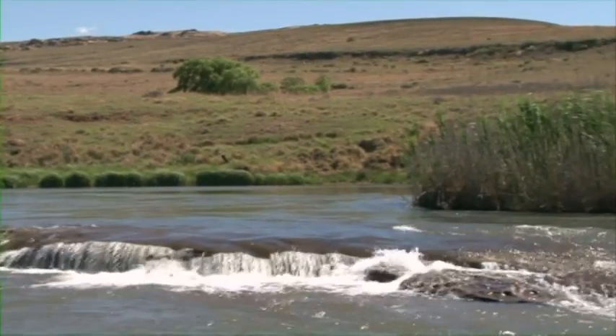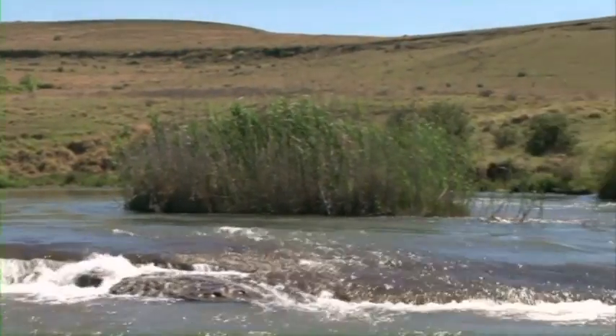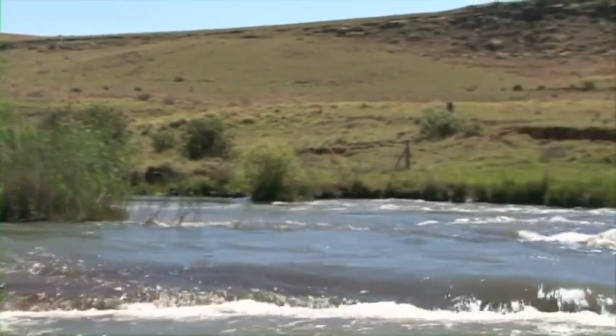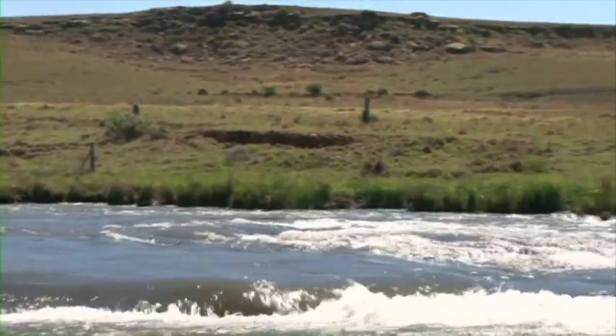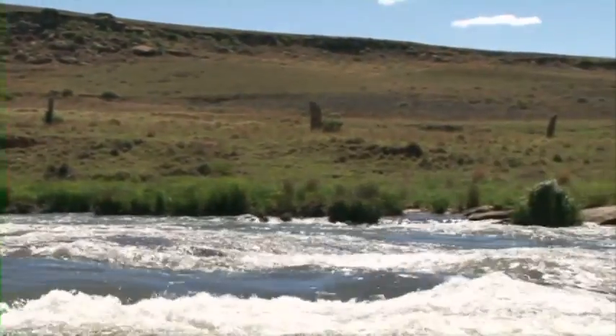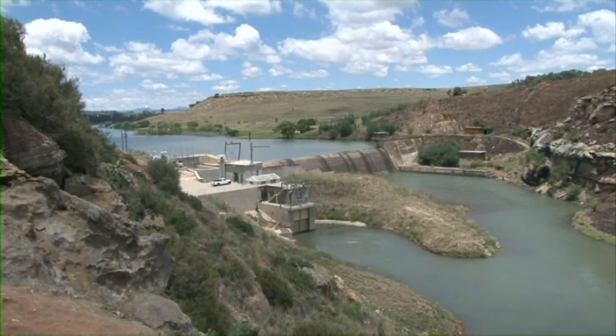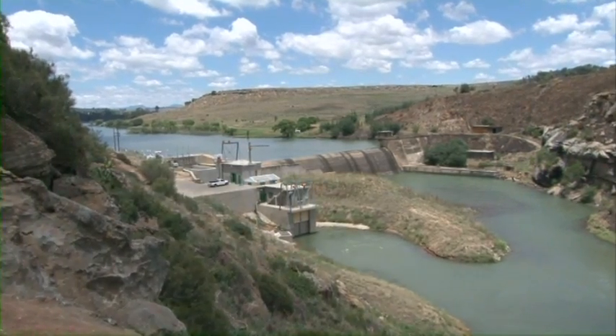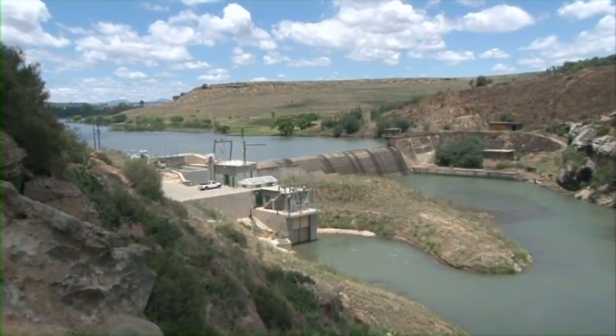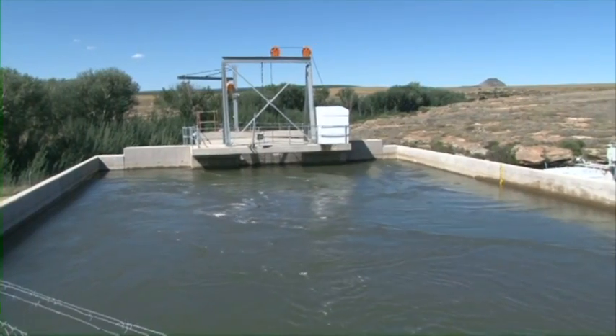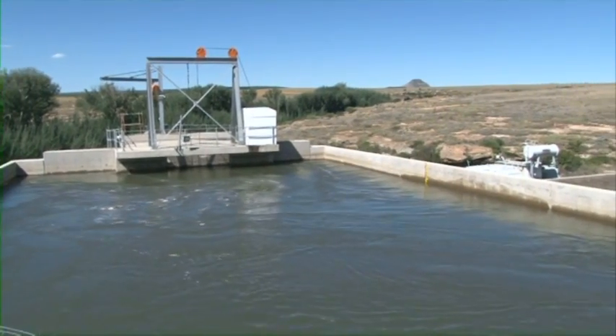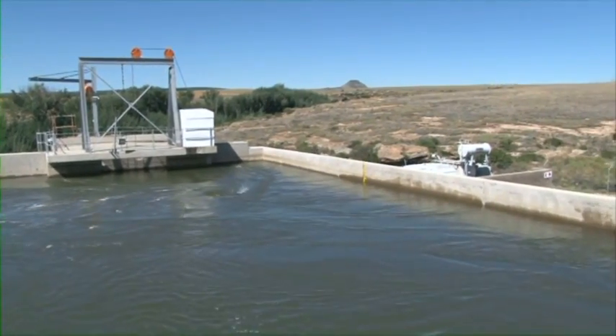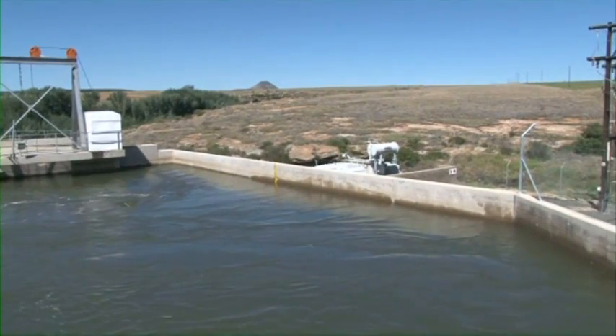The Bethlehem Hydro project has identified the Ash River as a suitable river for this project because of the constant flow that comes through the Lesotho Highlands water scheme. A constant flow of 27 cubic meters per second flows down the river, all the way from the Ash River and down into the Solplaatjie Dam. Bethlehem Hydro has two projects installed on this Ash River. One is called the Solplaatjie Power Station and the other is called the Merino Power Station. The Solplaatjie power station is rated at 3 megawatts and the Merino power station at 4 megawatts.